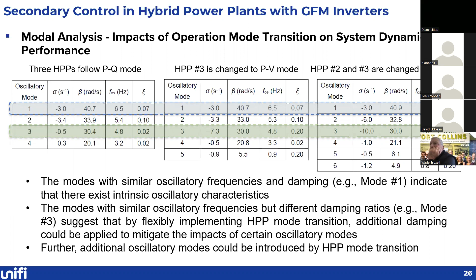There are some additional case studies we would like to highlight. In this system, for small signal stability analysis with varying penetration levels, when penetration is smaller than 70%, the system is stable with a below-0 stability margin. Unfortunately, for the original system with all HPPs set in PQ mode—and as a side note, the synchronous generator is set as V-delta mode—the system becomes small signal unstable with larger than 70% penetration level of HPPs, the inverter-based resources.